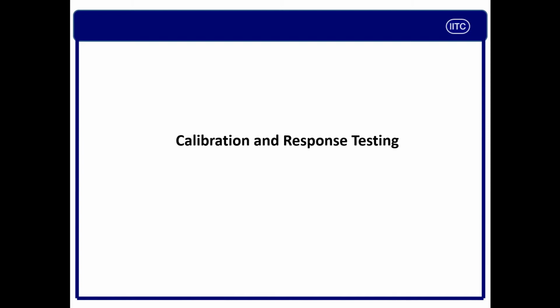This point is a very important point, calibration and response testing. All gas detection equipment shall be calibrated in accordance with the manufacturer guideline or local standard requirements. Point number 2, calibration results should be documented and maintained until subsequent calibration. Point number 3, in addition to routine calibration, following shall be done. Number A, the response check of the instrument shall be done. Number B, gas test shall be done before each work shift or each break. Before use of confined space, workplace, if not used for every work shift. So these are the 3 points where you need to do routine calibration.